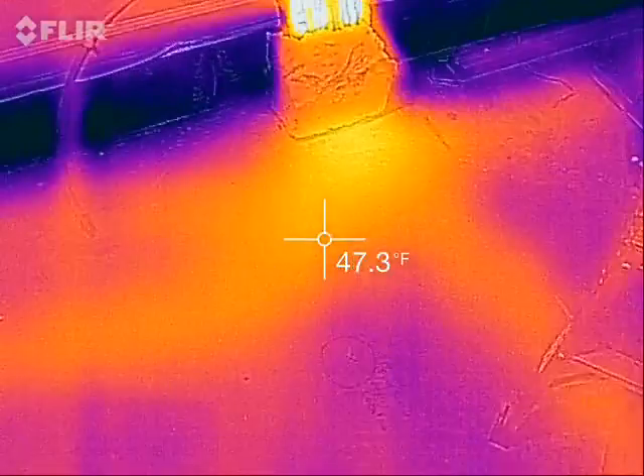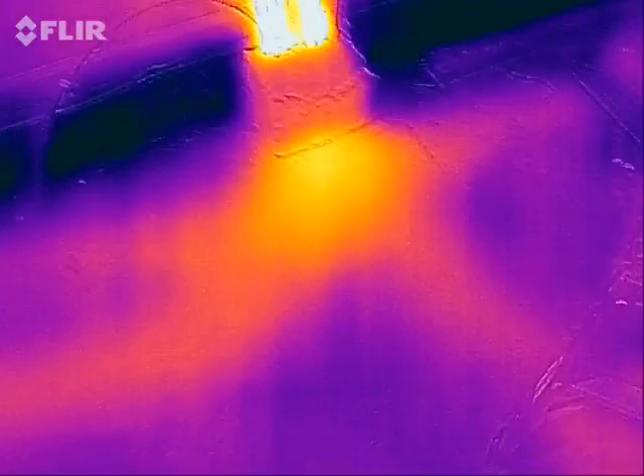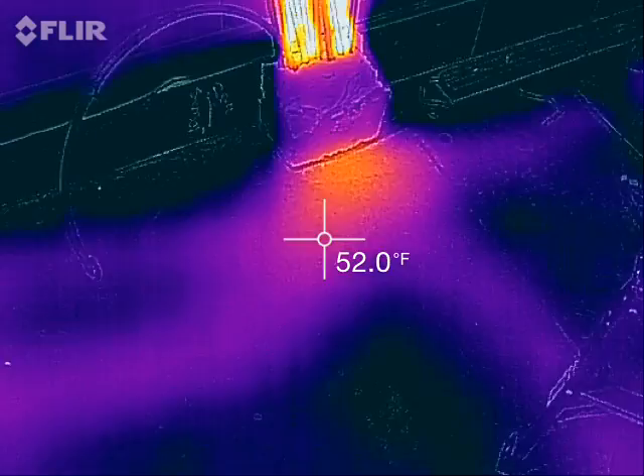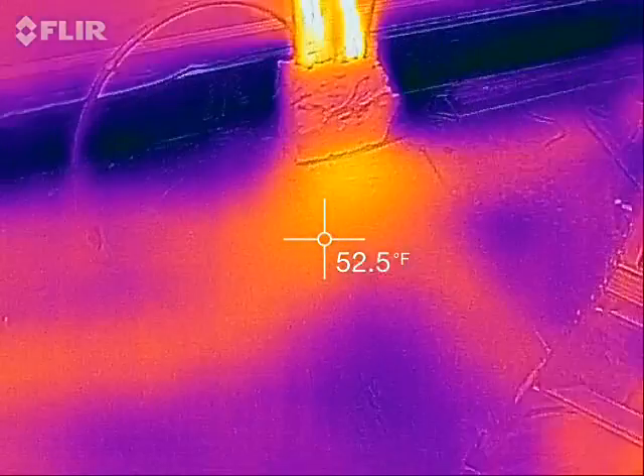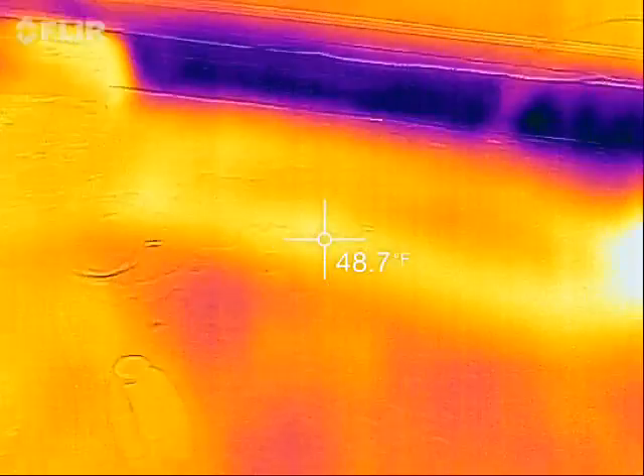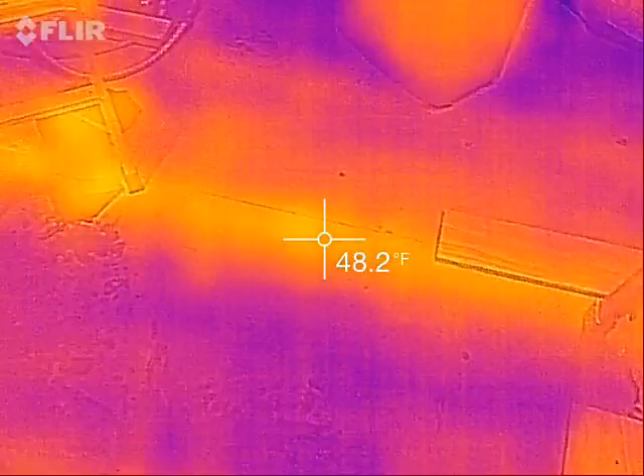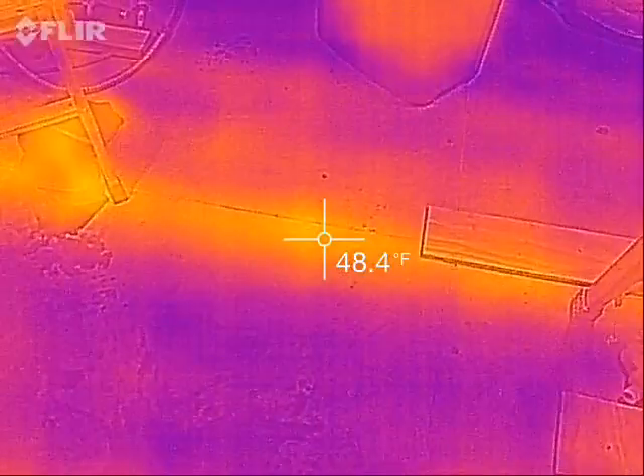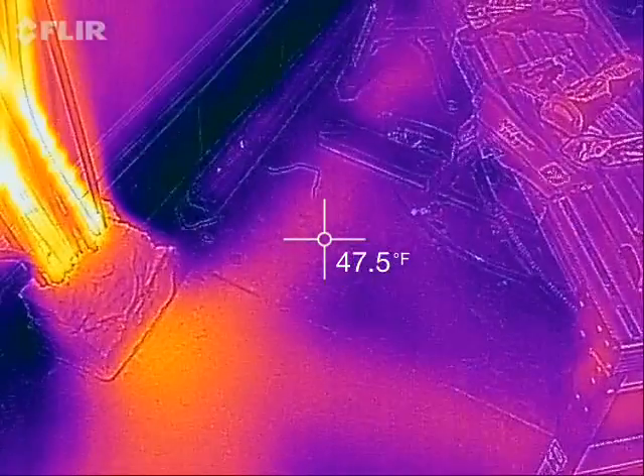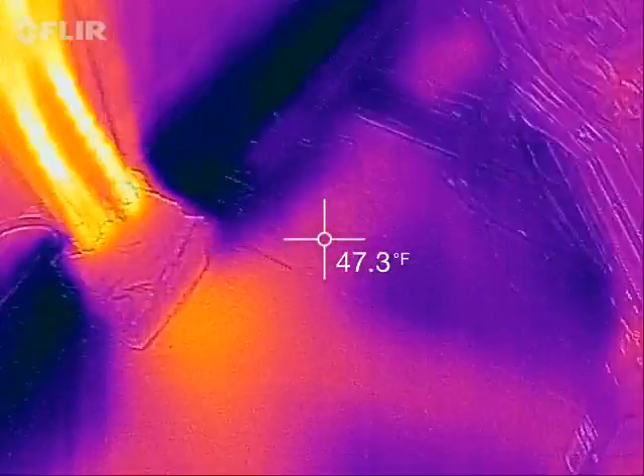It's kind of neat — you can actually see in the concrete how the heat radiates out from there, because the tubes are centered right here. Some go over this way to the first and second loop. We've got a branch right here which is both the return of the second loop and the start of the third loop, and over here we can even see going north to the beginning of the first loop.